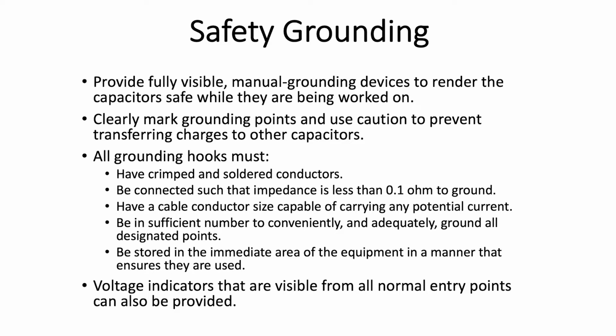Some of the grounding issues, if you look at what the manufacturer suggests in terms of fully visible manual grounding devices to render the cap safe while they're being worked on, clearly mark the grounding points and use caution to prevent transferring charges, as we said. All grounding hooks must have crimped and soldered conductors, be connected such that the impedance is less than 0.1 ohm to ground, have a cable conductor size capable of carrying any potential current, be in sufficient numbers to conveniently and adequately ground all designated points, and be stored in the immediate area of the equipment in a manner that ensures they are used. This is what the OSHA inspector's checklist looks like.